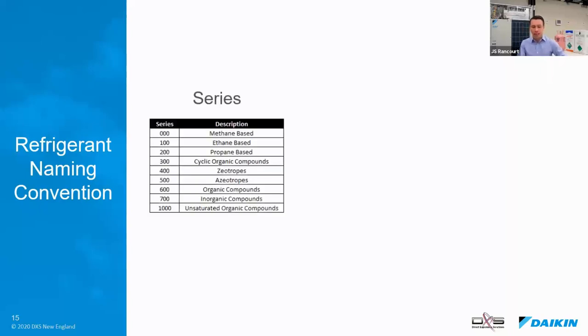First, let's talk about the naming convention. You're gonna hear the word R dash something a lot, R50, R22 beside me, R410A. So there is some method to the madness. There's different series from 0 to 1,000. The methane series, R50, fits in there. There's a propane series. Propane is R290, it fits in there. R410A is a zeotropic mixture. It's a 400 series refrigerant. Water is R718, it gets a number as well. And that's a 700 series.